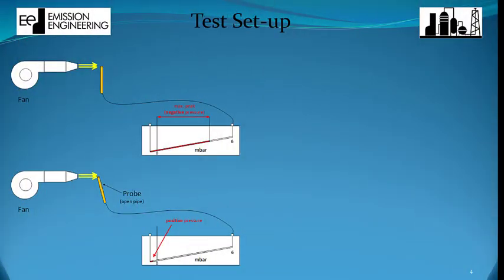In the next video you will see how wind will affect the transmitter. The second, or reference, branch of the transmitter, respectively the tubing, is here simulated by a handheld tube of 6 millimeters. Though it doesn't really make a difference whether it is 6 or 12 millimeter tubing.